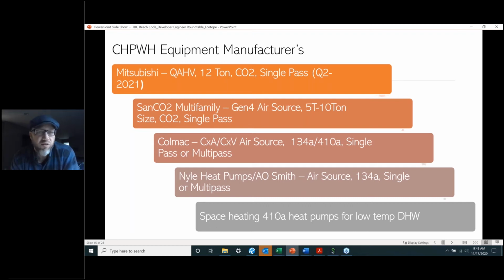So Colmac has a CXA and a CXV. Both are air source devices, with an outdoor temperature range they operate on. Nyle and A.O. Smith have similar products, both air source 134A, single or multipass. And then the fourth class would be your typical space heating 410A heat pumps that we put heat exchangers on and do low temperature DHW.